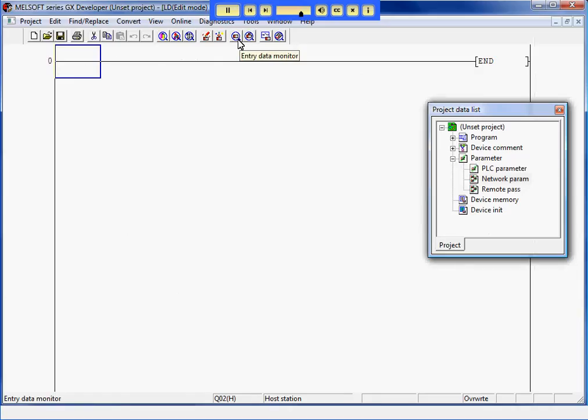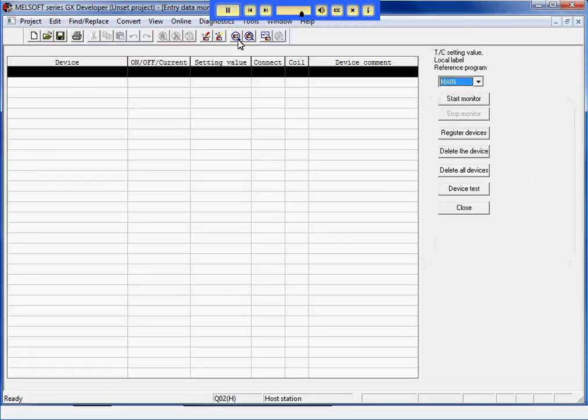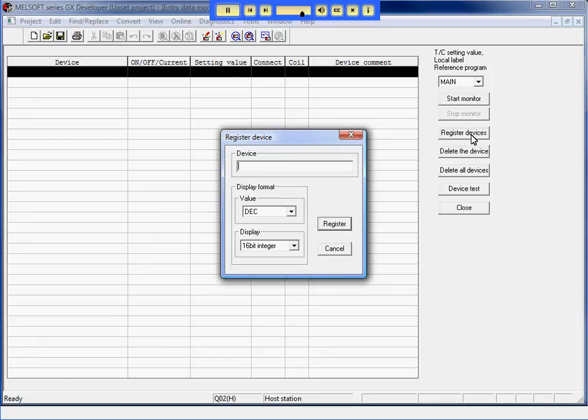I will use the Entry Data Monitor to monitor the different devices on the PLC. First, I will monitor D100, which I set up in the network parameters. I will set up devices for each of the PATMAX results, and set them to real numbers to match the settings in In-Sight.